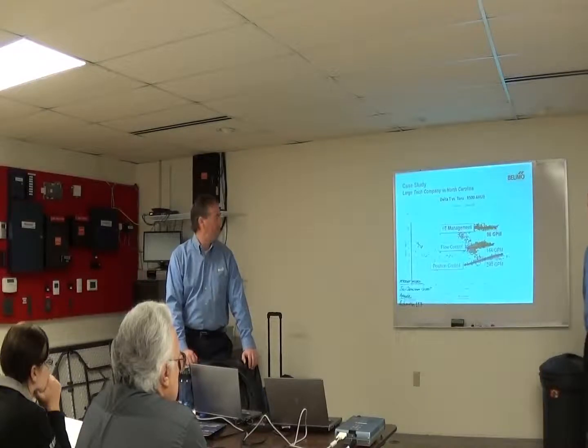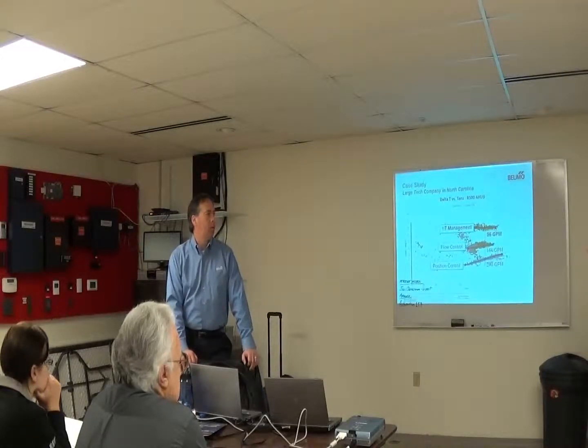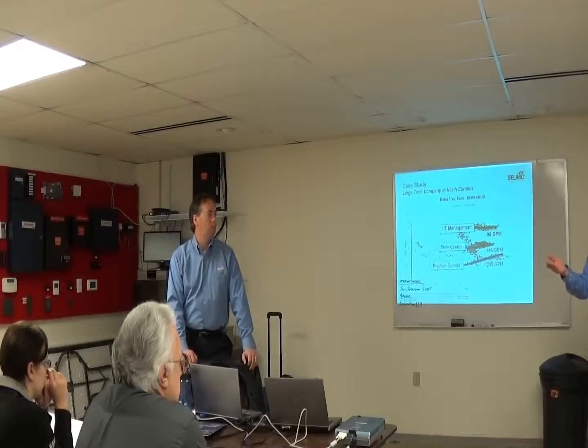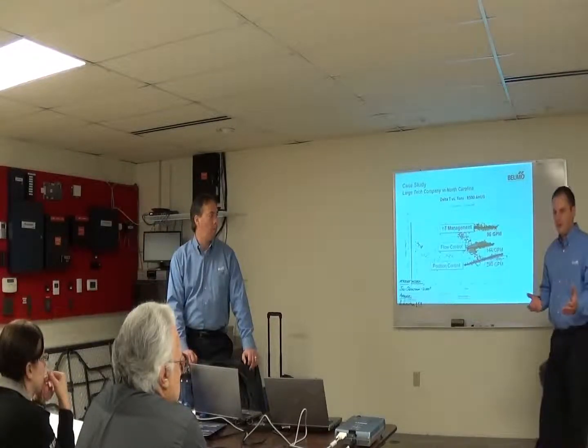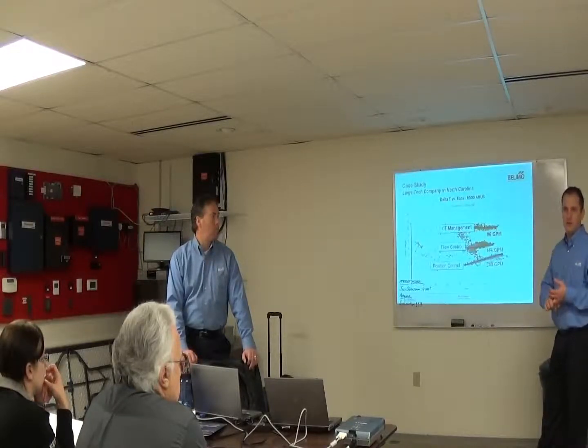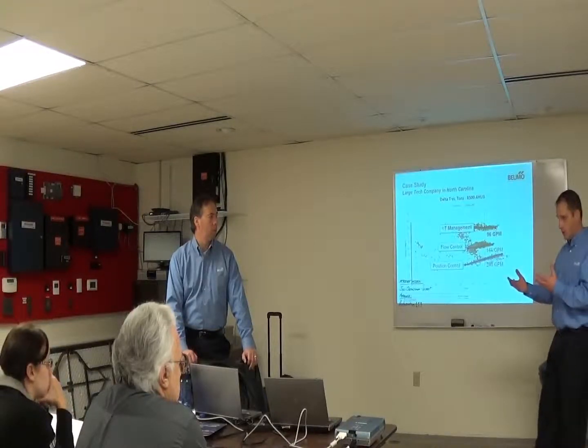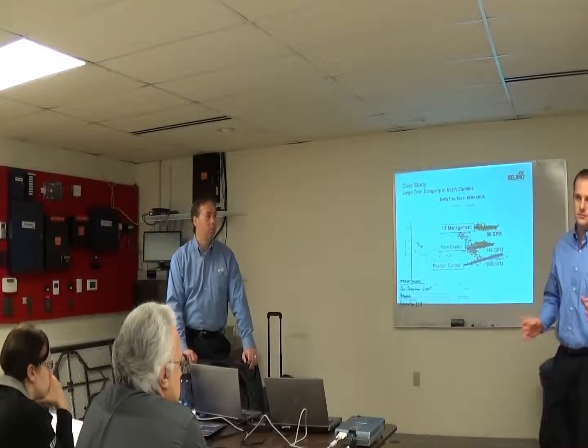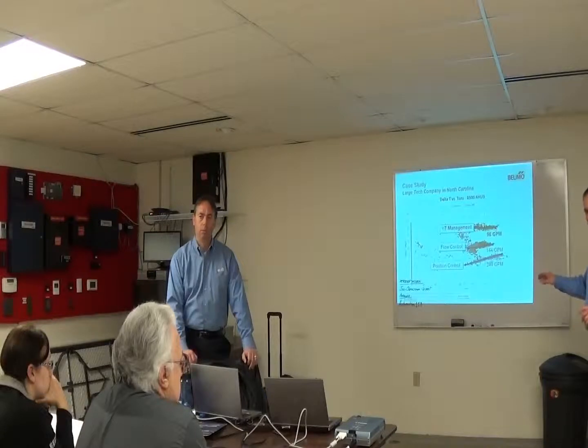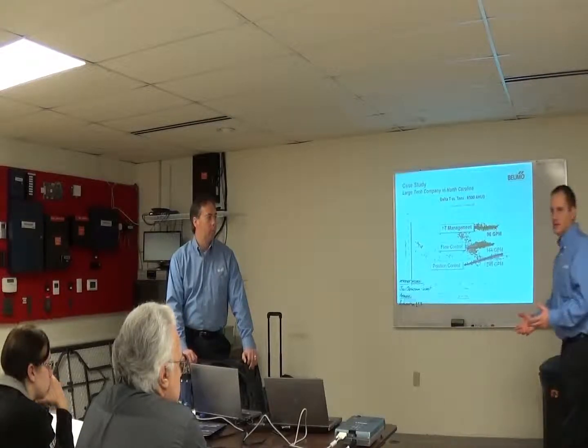But, so you've got pressure dependent, say 15%, you've got EPIV, 15% more cost, you've got energy valve. I'll tell a lot of people to put the energy valve on all your big air handlers. I've got one job where they're putting them on every VAV box. It's a new school going up, they're gonna put these on every coil. But if the cost is an issue, put these on your big coils. Maybe put the EPIV on some of your medium-sized coils or smaller coils. And then put mechanical pressure independent on everything else. Just make it all pressure independent, so you get that savings, but you don't have to have a BTU meter for every VAV box. You add all those VAV boxes up, and they're bigger than probably any area in the building, right? So it's still a considerable amount of energy, but space becomes an issue, cost might become an issue.